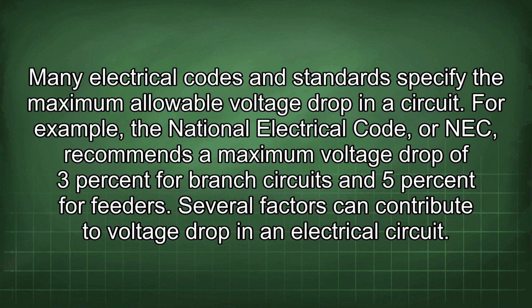Many electrical codes and standards specify the maximum allowable voltage drop in a circuit. For example, the National Electrical Code, or NEC, recommends a maximum voltage drop of 3% for branch circuits and 5% for feeders. Several factors can contribute to voltage drop in an electrical circuit.